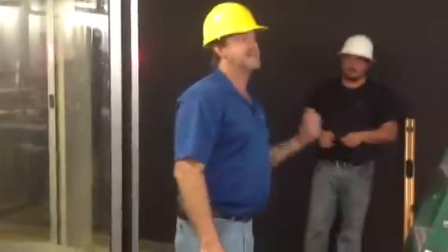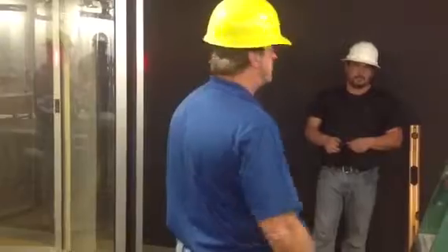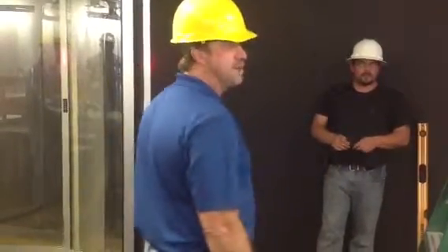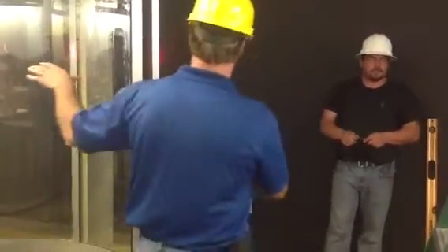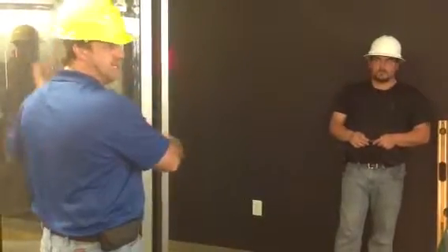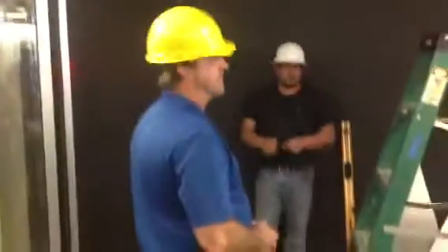So I'm going to ask the obvious question. You guys put the switch there for a reason. Yes. What are the indicators that you might need to reset the stereo vision camera? If the door ends up in the plus position and starts acting funny, sounding an alarm, and it's stuck in the plus position, reset the stereo vision camera system, and the door will spin, find its home position, and then the camera will boot back up, and the rest position will be correlated back again with the PLC. It's very rare that that ever has to happen, but there are some occasions.